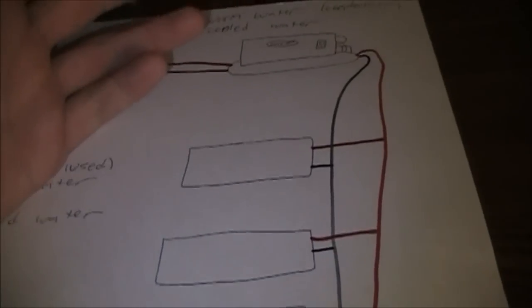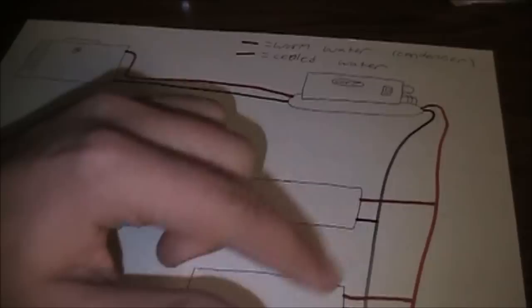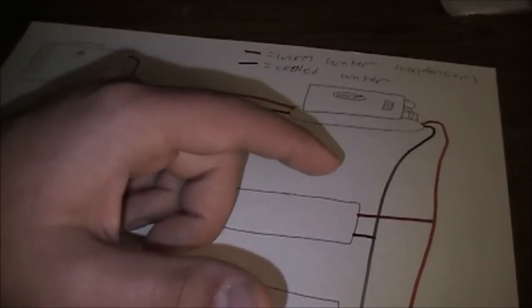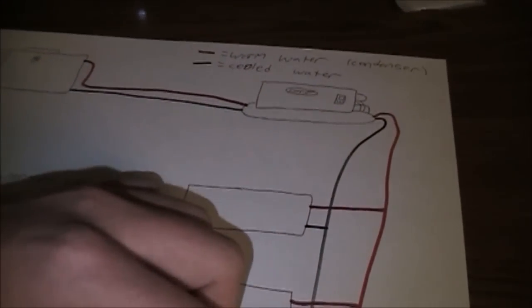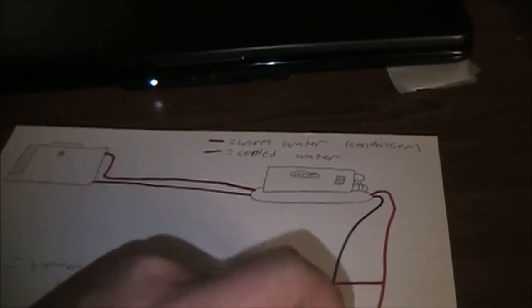But this black represents the chilled water, which is usually around 43 degrees Fahrenheit somewhere around in there, going to the coils and the air handlers. And then you got the water returning to the chiller to be chilled again. This water is usually around 50 degrees, sometimes over, depending on load.